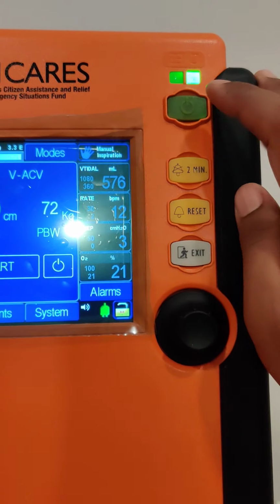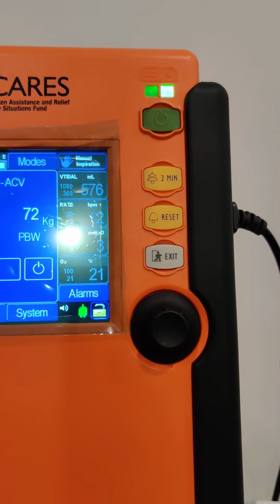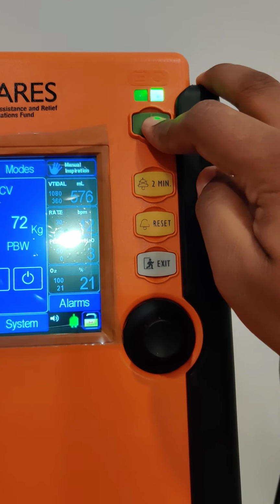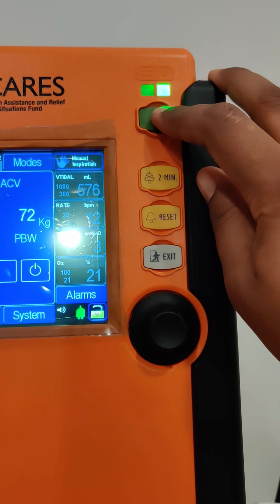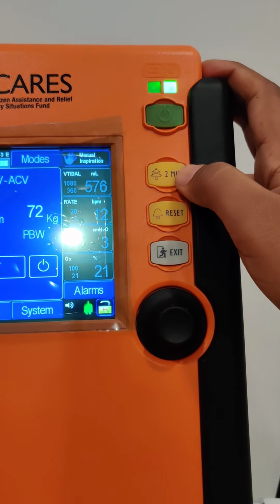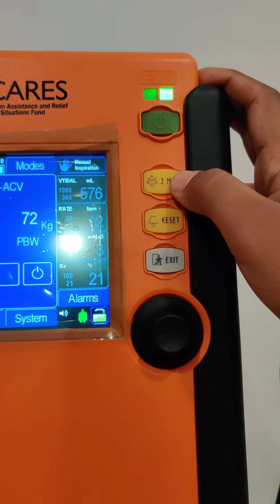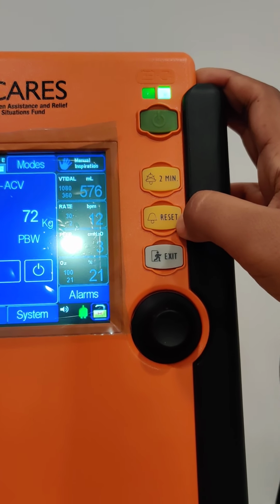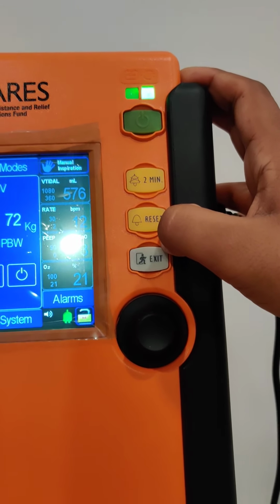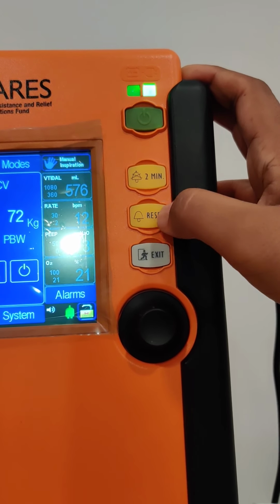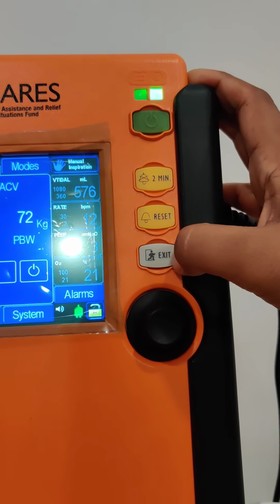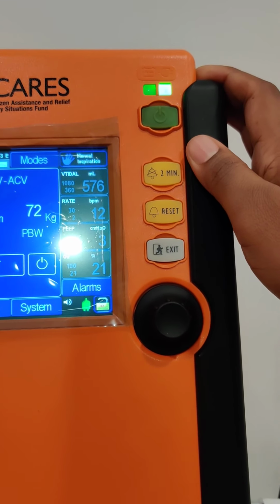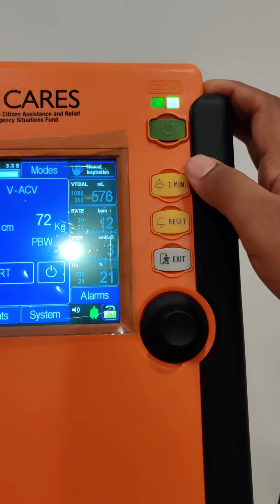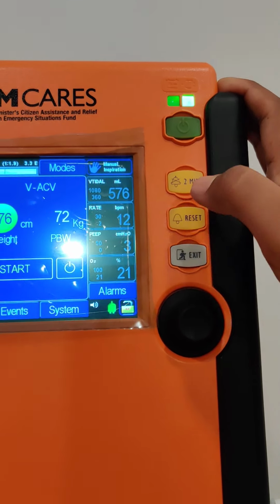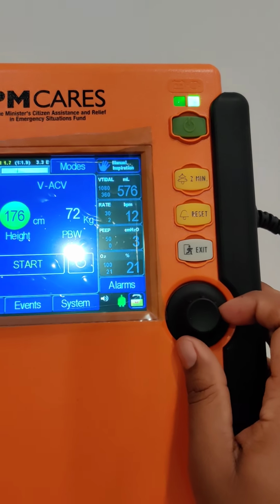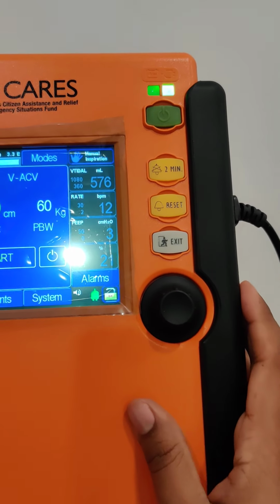Now I am going to discuss the keypads or the key buttons which are available on the ventilator. This you have already seen in the video, that this is for turning on and turning off the ventilator. This button is used for silencing alarms; whichever alarm is coming, that alarm can be silenced for 2 minutes by pressing this button. And this is for resetting the alarms. If any alarm has come up and you have not seen it and you have to acknowledge those alarms, then you can use this reset button. And this exit button is used if you have gone into some settings or any modes of ventilation and you want to exit from that window. And this is the knob for increasing or decreasing the values as well as for confirming the values.